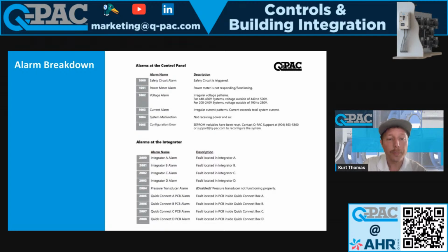Current alarm, if you have some weird current patterns that go beyond what you should be getting, then that alarm will throw. The EEPROM variable. So this is, again, not a very common alarm, but if that alarm does occur, then it's actually a really simple fix. You just have to call our technical support team, and they will give you a code to go into the back end and change some settings. So it just means that something happened with the memory of the PLC, and it doesn't remember how many integrators or how many fans or the fan model. I don't really know why that would ever occur, but it does occasionally, though not very often.